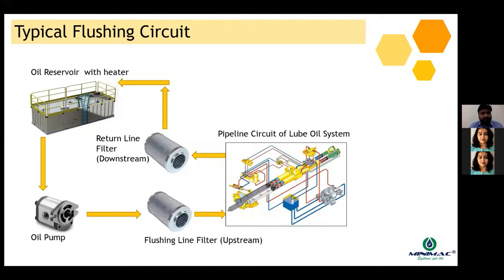It is better to have external flushing systems and not to use the lube oil circuit for performing the lube oil flushing activity. Because if you use the same lube oil pump for your oil flushing activity, there is a high chance that your existing auxiliary oil pump or the lube oil pump would be subjected to heavy debris, and that might reduce the lifespan of your equipment components.